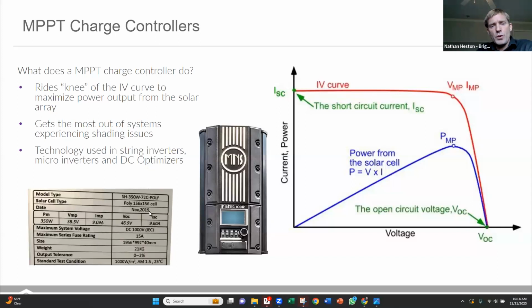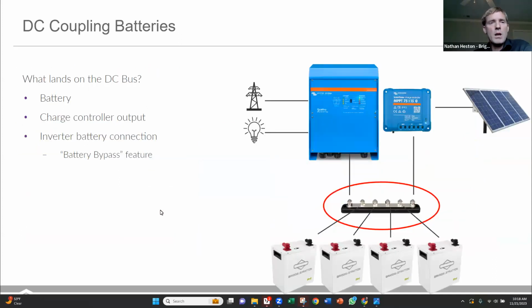You can also short circuit a panel. So a lot of people are nervous to short the positive and negative side of a panel together, but you should actually do that and test to make sure that you're getting somewhere around the short circuit current of your panel. You're not going to harm anything in the panel by shorting it out. It's just going to produce its maximum amount of current. And if you have a DC amp clamp, you can check that current when you're checking your solar panel.